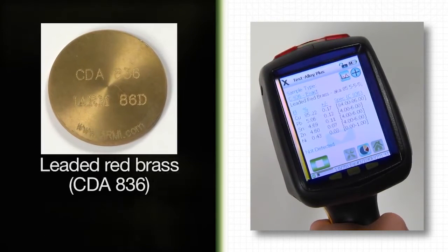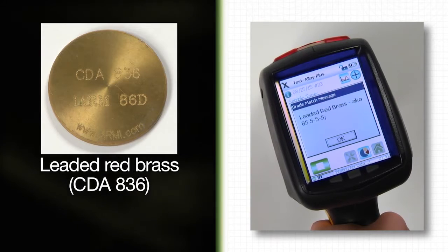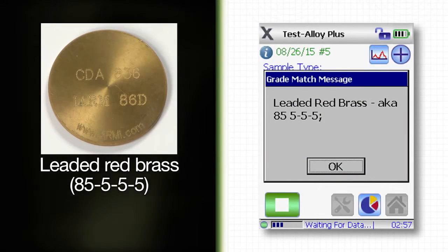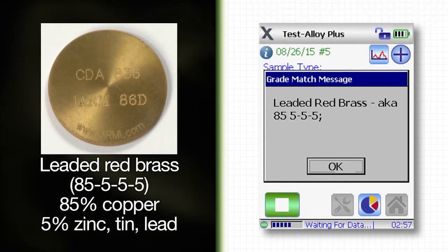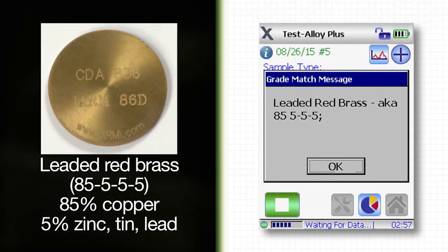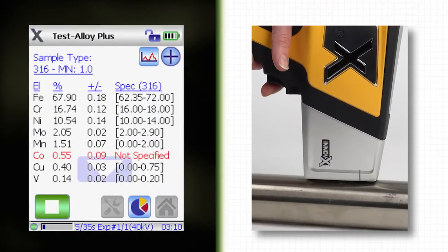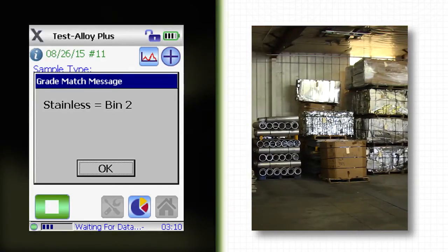This example is a leaded red brass, CDA 836. The grade match message shows the common grade name, 85-5-5-5. This refers to the concentration of 85% copper and around 5% each of zinc, tin, and lead. This is useful if your employees are more familiar with the common names. Or you could add instructions that are specific to a task, in this case marking material for later handling.